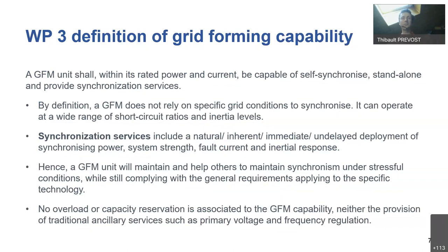Okay, let me pass through this slide. So for a grid forming unit, at least in our project, we consider that it should not be oversized. It should provide, within its power and current limits, synchronization services standalone, and be able to self-synchronize. So it does not rely on specific grid conditions to synchronize and can operate on a wide range of short-circuit ratio. What we call synchronization services are the very, very fast services, so we can say natural, inherent, immediate. It's basically what we call synchronizing power, the system strength, fault current, and inertia. We'll go through that just later.